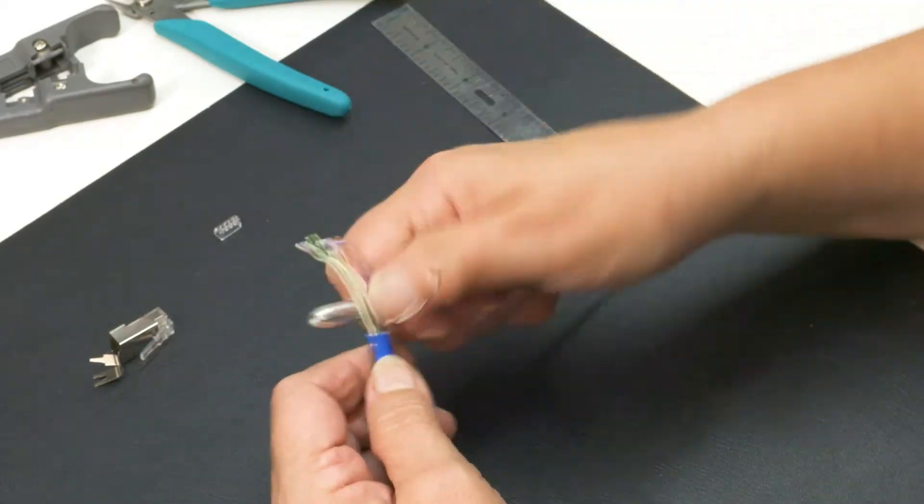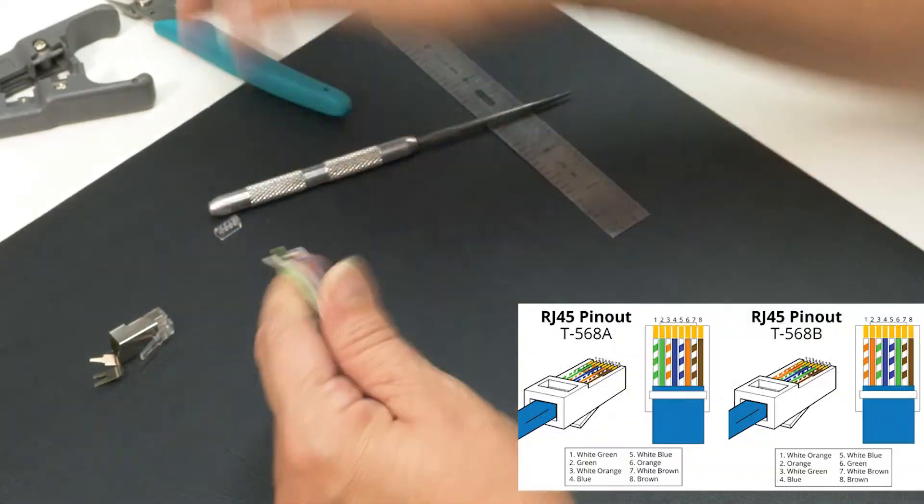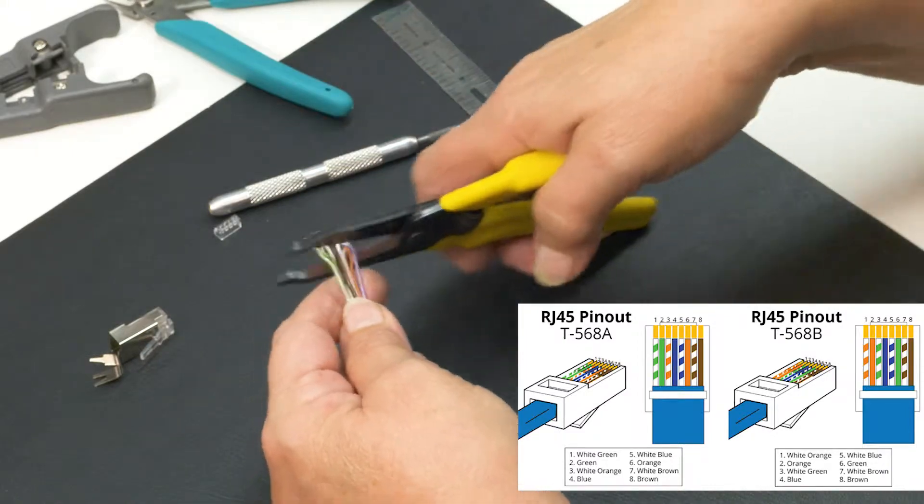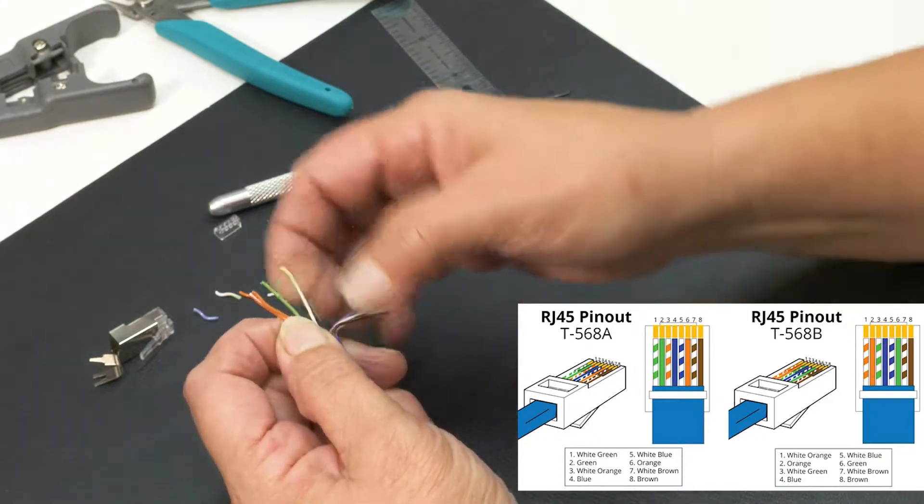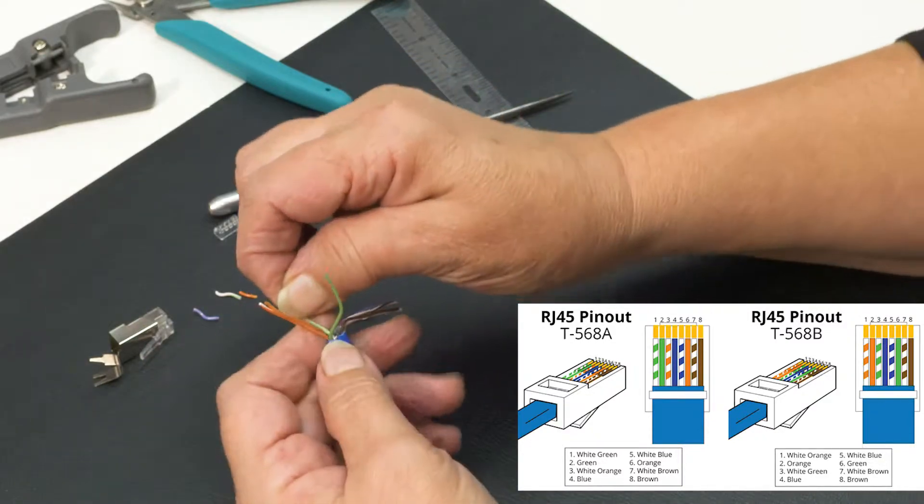Straighten out the conductors as smoothly as possible to get all the twists out. Organize the wires in the proper color code based on the wiring standard you're using. In this case, we're using T568B, which is for commercial and business applications.